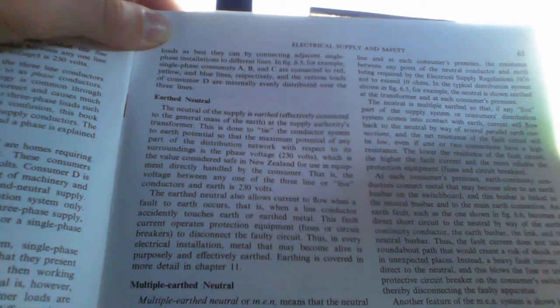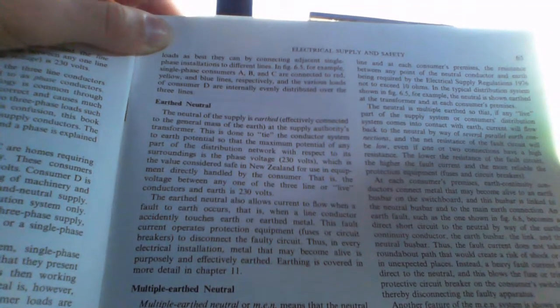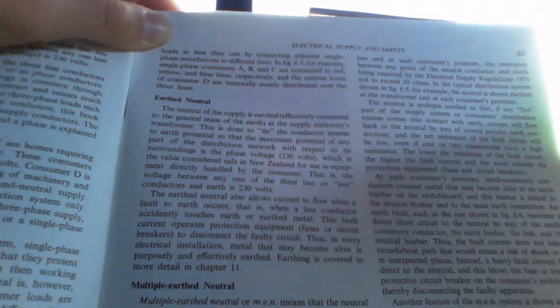So, this is just natural light. Earth neutral. The neutral of the supply is earthed effectively connected to the general mass of the Earth and supply authorities transformer. This is done to 'tie' the conductor system to the Earth potential, so the maximum potential of any part of the distribution network with respect to its surroundings is the phase voltage, 230 volts, which is the value considered safe in New Zealand for equipment directly handled by the consumer. That is, the voltage between any one of the 3 line or live conductors and Earth is 230 volts.